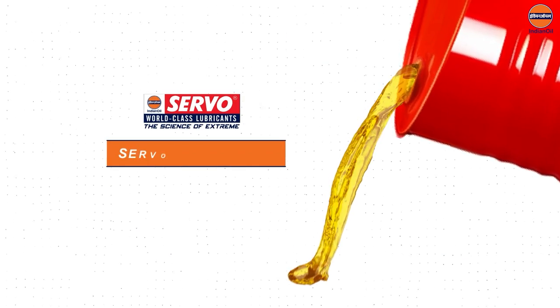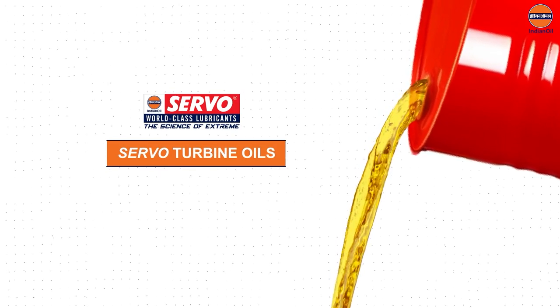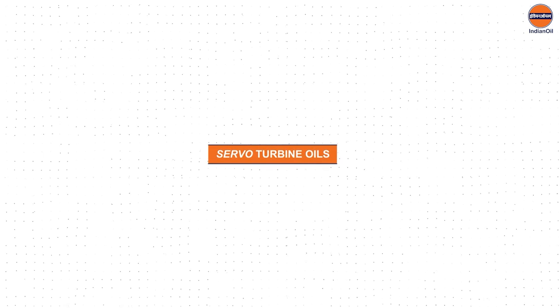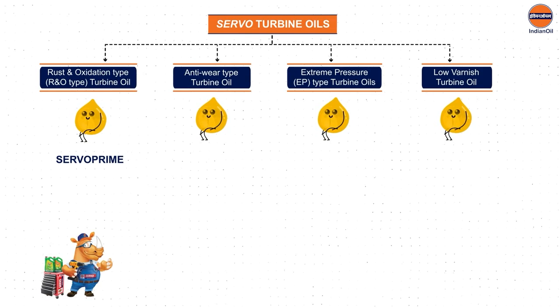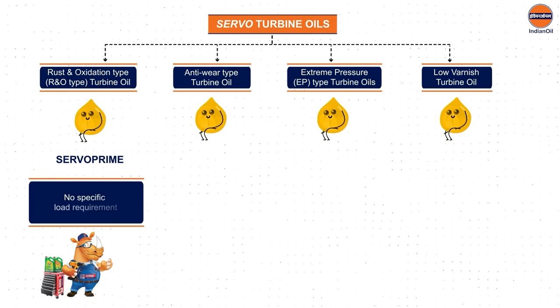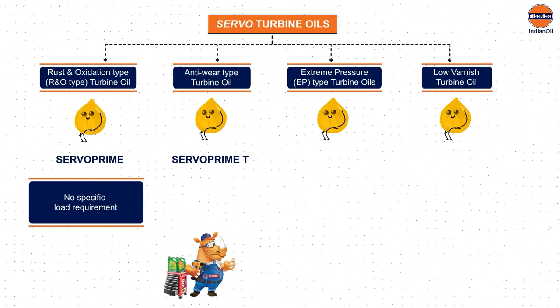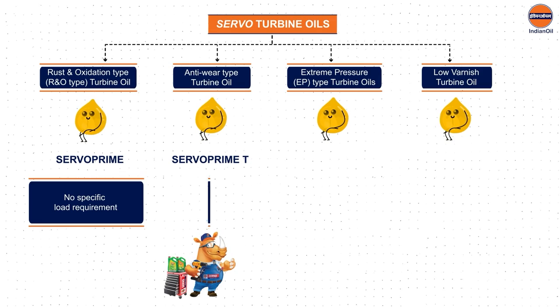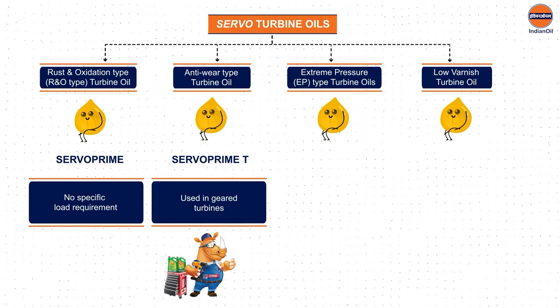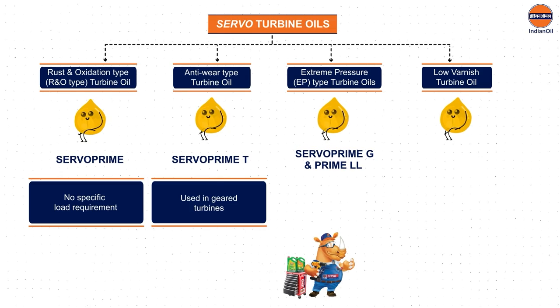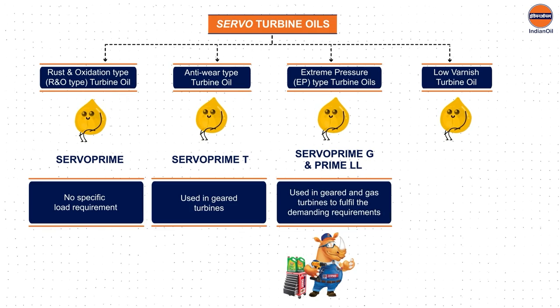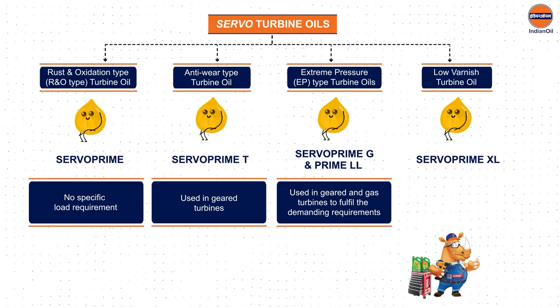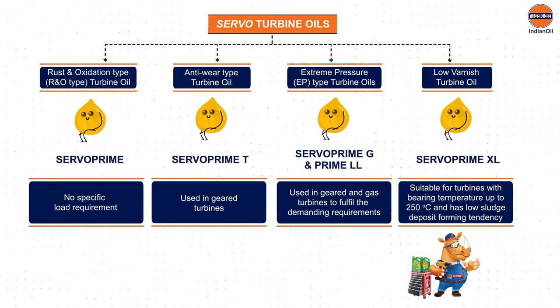Let's look at the turbine oils offered by Indian Oil Servo. Indian Oil Servo offers a range of turbine oils categorized into four segments. Servo Prime is the rust and oxidation type turbine oil without any specific load requirement. Servo Prime T is similar but has anti-wear properties and is used in geared turbines. Servo Prime G and Prime LL are extreme pressure type turbine oils used in geared and gas turbines. Servo Prime XL is the low-varnish turbine oil suitable for bearing temperatures up to 250°C with low sludge deposit forming tendency.